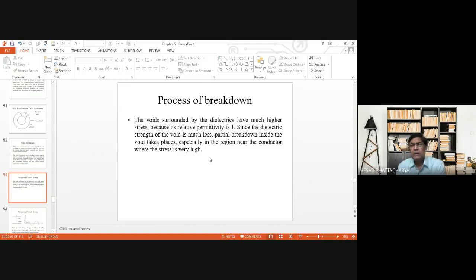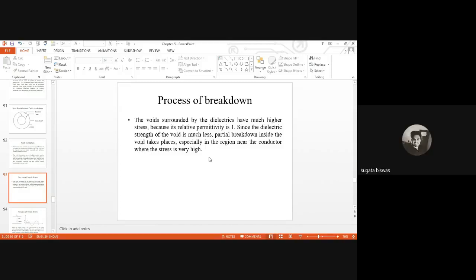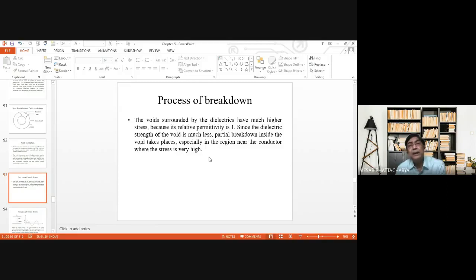Yes, sir. Now, if this happens repeatedly, then what will happen? The solid insulating material on either side of the void, that is, the material in contact with the void, will be burned, and this burning will extend in either direction slowly. Is that okay? Yes, sir. And finally, a time may come when this burning of the solid insulating material may extend in such a way that it may short circuit the conductor core with the outer sheath.